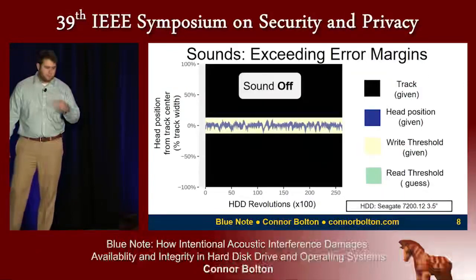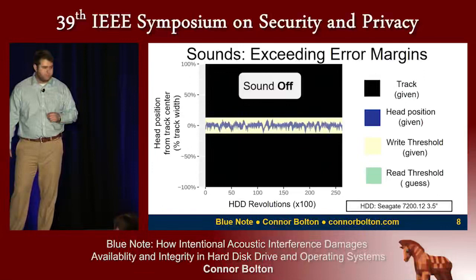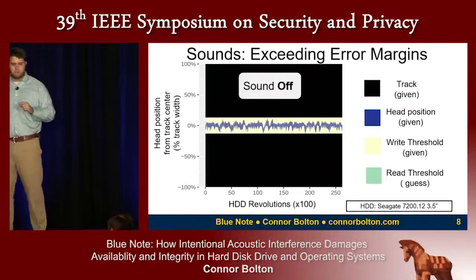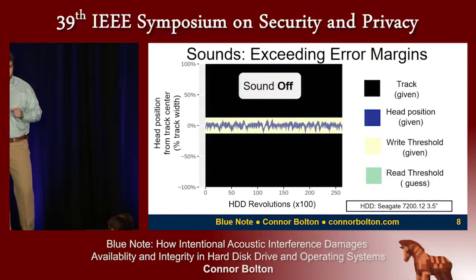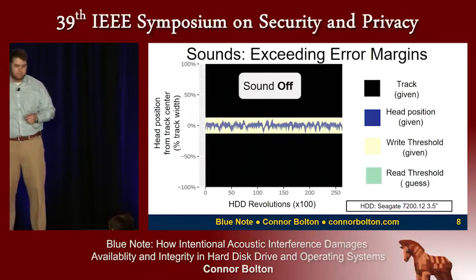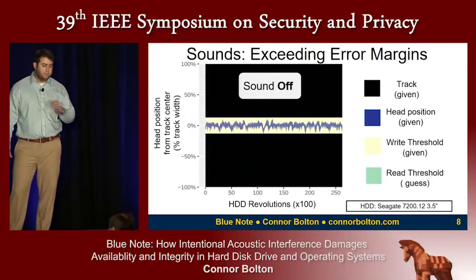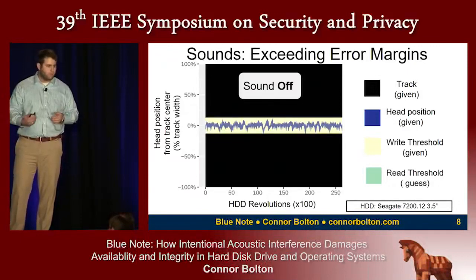We took a hard disk drive and used a diagnostic port to look at the actual position of the read-write head relative to the center of the track, at 0% in this graph. The position of the read-write head, shown in blue, needs to stay within the yellow strip in order to work properly, in this case to write properly.